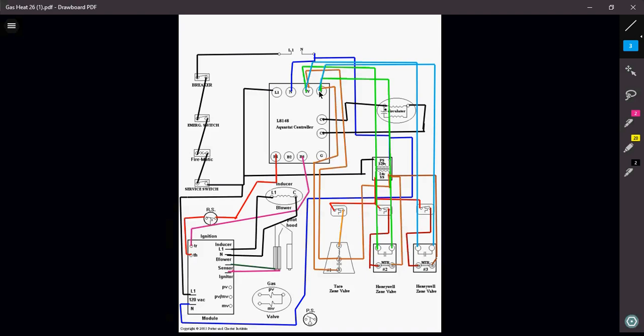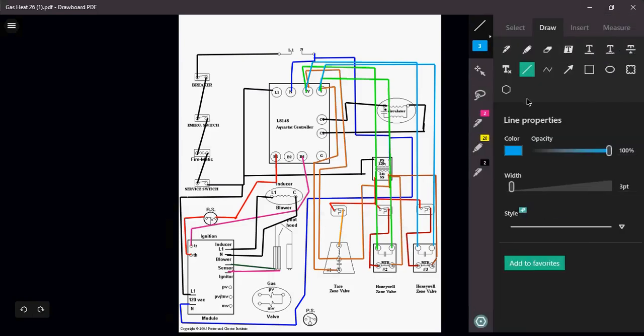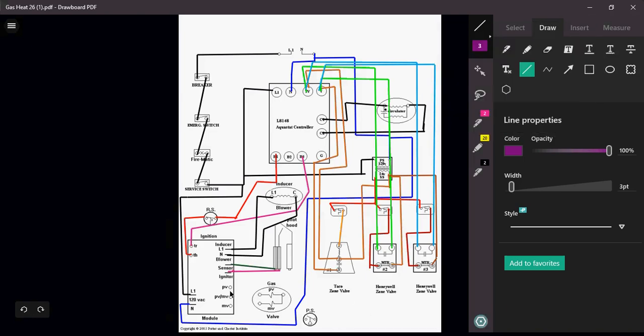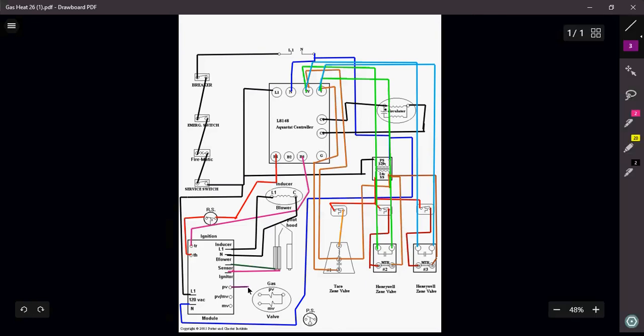The last thing that we really have to take care of in this is obviously the gas valve. We haven't taken care of that yet. I have a gas valve and a pressure switch. So what am I supposed to do with this stuff? Well, we got to look at it from a standpoint that a pressure switch is nothing more than a safety. That pressure switch is going to be used to prove whether or not that vent blower has actually started to spin and that the combustion chamber itself is actually clear of any combustible gases.